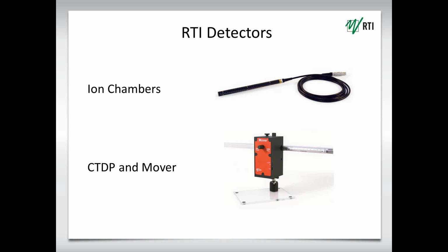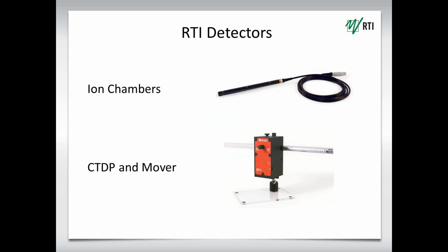Ion chambers. We can use CT ion chambers. We can use mammo chambers, whatever chamber you want to use. For CT, you can use it for your CTDI measurements. For the mammo, you can do all your mammo dose measurements. And as someone has already said, we give complete waveforms so you can see the dose rate waveform right off the ion chambers. We also have our CT dose profiler, which gives you dose profiles. That's a real benefit if you want to see what's happening with the dose profile in the CT scanner. And we've got our mover, which allows you to do your axial scans as well.